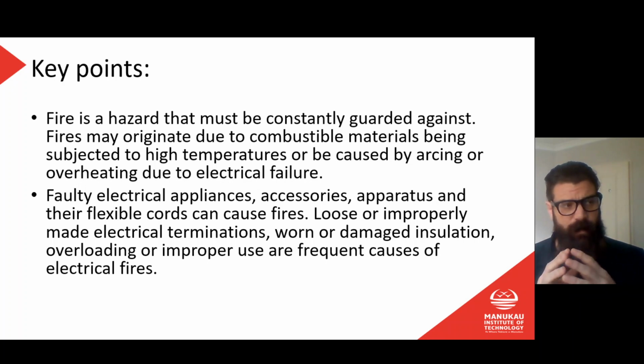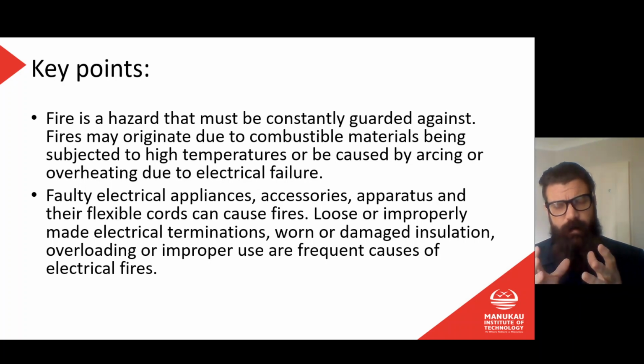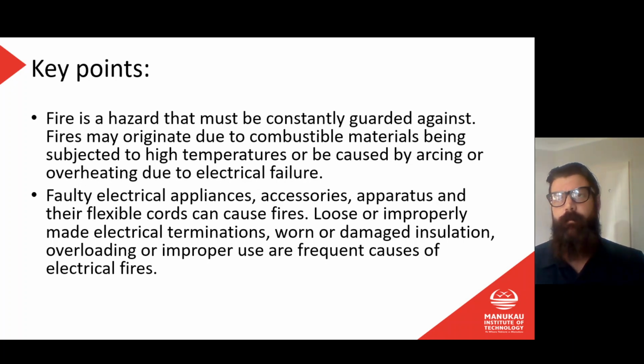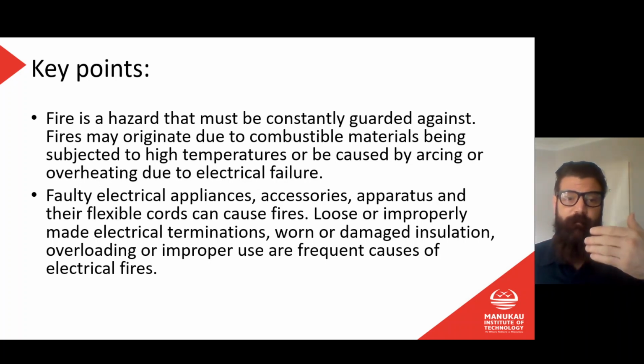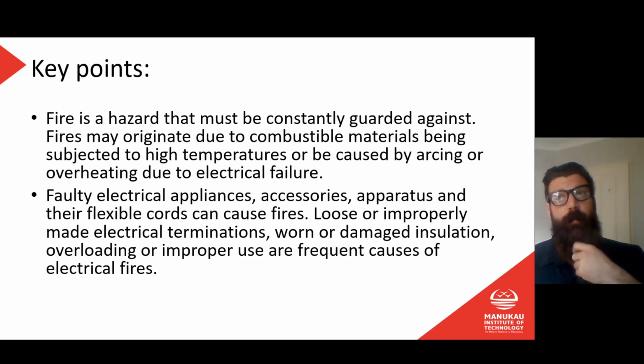And while we're talking about that, so what are we talking about here? Why does overloading things or bad connections cause heat and potentially fire in the future? Now, if you think about, we've talked before about the concept of resistance. What is resistance? If you have current flowing through a wire, it's going to cause heat. It will always cause heat. There'll be heat caused by current flow through a conductor. Now, the greater the resistance of that conductor, the more heat that will be generated. It's dissipating power. It's consuming power as heat.